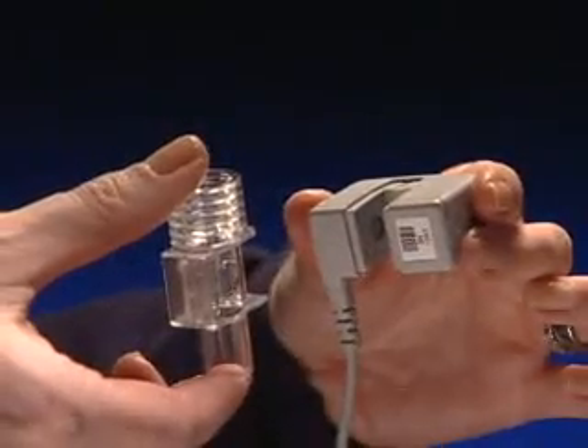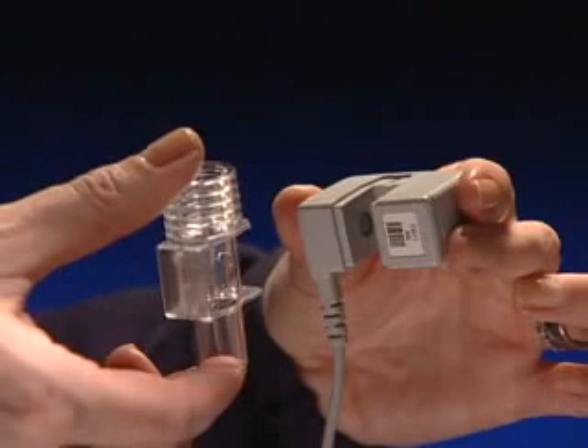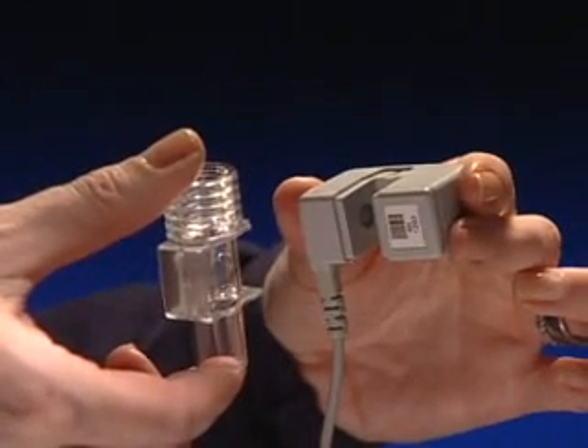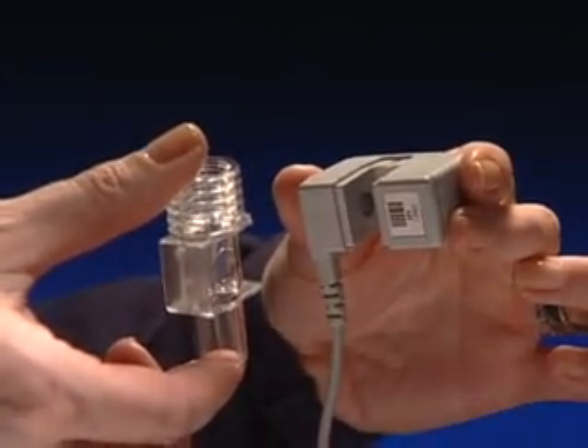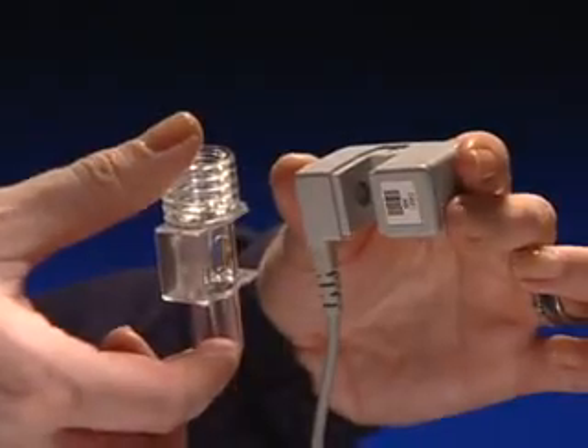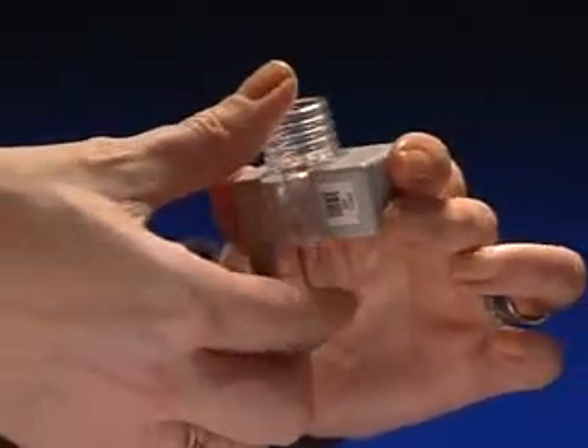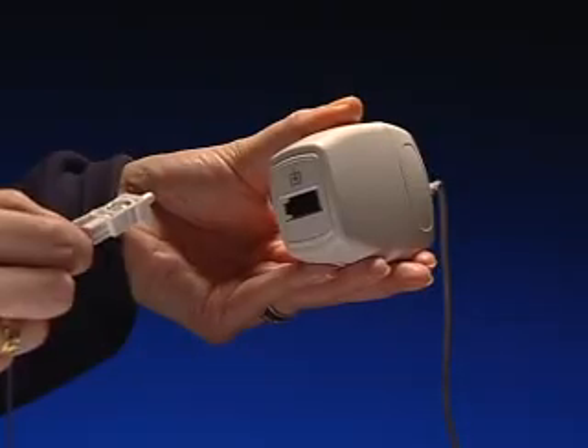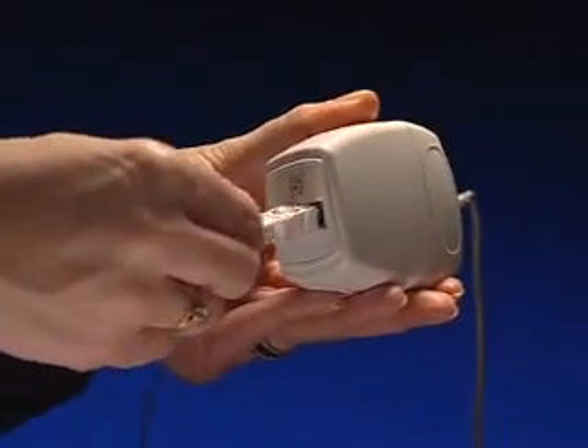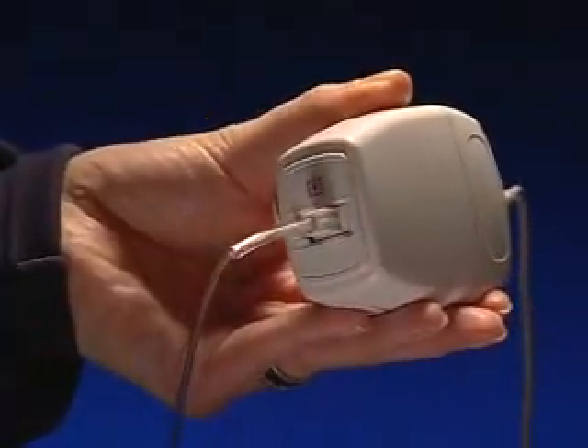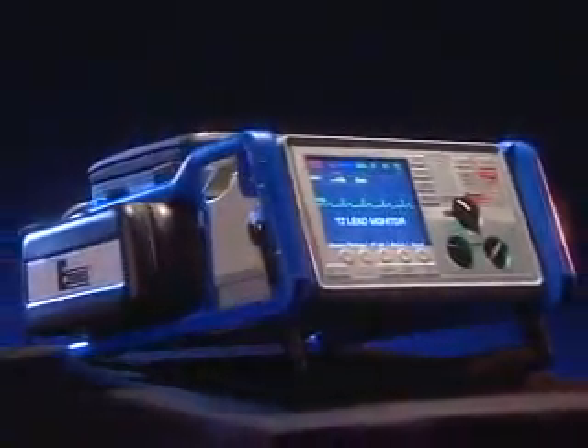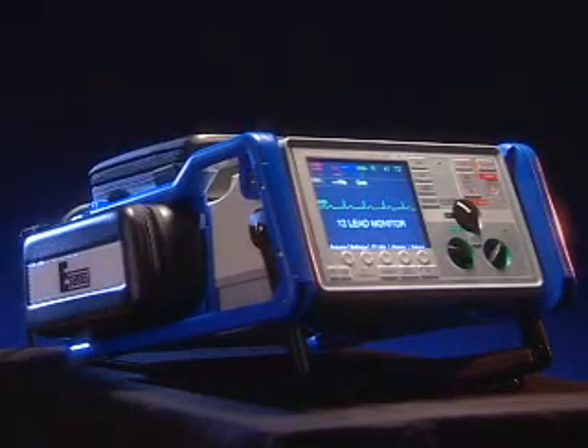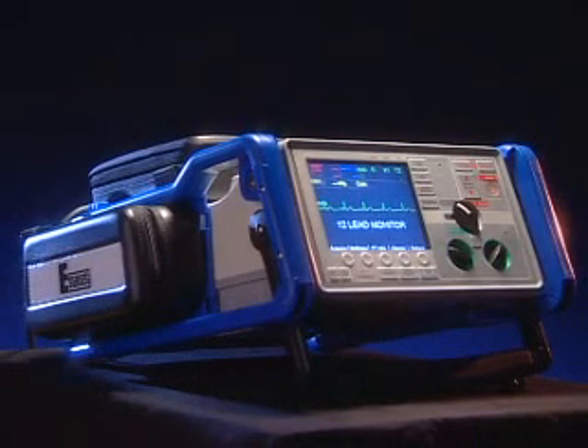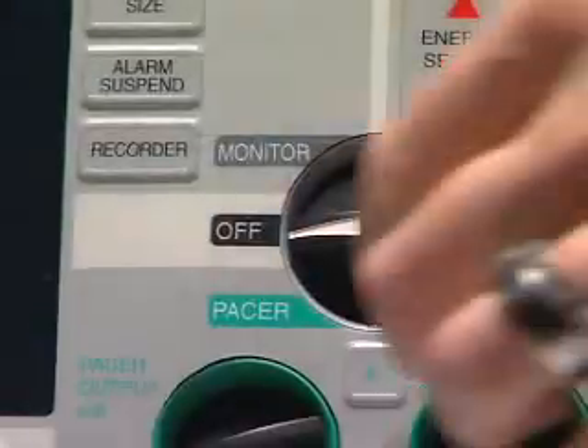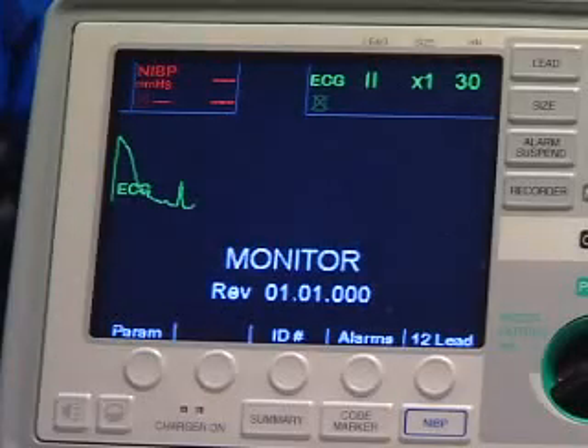Attach the airway adapter to the Capnostat 5 mainstream CO2 sensor by aligning the arrow on the airway adapter with the arrow on the bottom of the sensor. Then press both the sensor and the airway adapter together until they click. For sidestream use, select an appropriate patient cannula and plug into the connector on the Capno 5 sidestream module. The E-Series is the only defibrillator able to offer both mainstream and sidestream interchangeable options on one device. Turn the E-Series unit to Monitor, on for AED units.